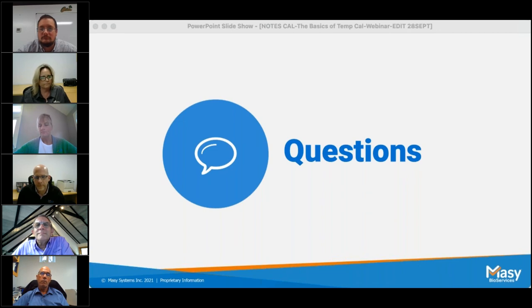Great, thanks. Okay, what determines calibration frequency, and how do I know at what interval I should calibrate? Who hasn't answered one yet? Matt, you take this one? Yeah, absolutely. Calibration frequency is based on a number of factors. Primarily, the criticality of the instrument in what it's measuring, the historical performance of the device, and even process runtimes can all be factors in the frequency of your calibration. In general, these intervals are all about risk. It's risk to the company, it's risk to the product, and it's risk to the patient. So it really is up to the engineers, the metrologists, and your QA department to work together to figure out what the best calibration frequency is for the instruments that you're using.